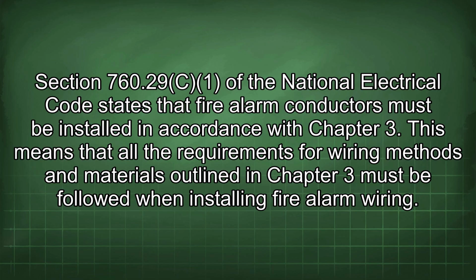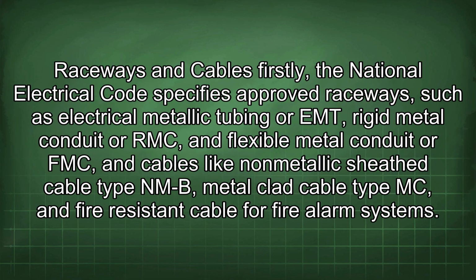Section 760.29 of the National Electrical Code states that fire alarm conductors must be installed in accordance with Chapter 3. This means that all the requirements for wiring methods and materials outlined in Chapter 3 must be followed when installing fire alarm wiring. Raceways and cables. Firstly, the National Electrical Code specifies approved raceways such as electrical metallic tubing, or EMT, rigid metal conduit, or RMC, and flexible metal conduit, or FMC, and cables like non-metallic sheathed cable type NM-B, metal-clad cable type MC, and fire-resistant cable for fire alarm systems.